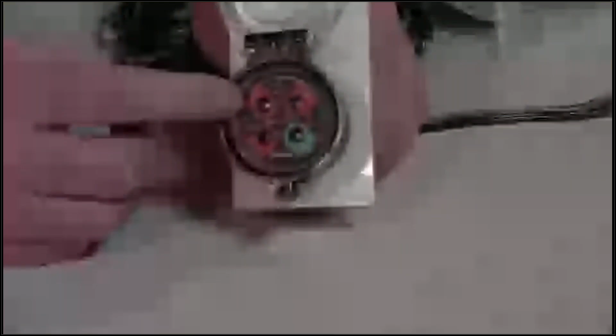Now, again, there's a little bit more involved with the live dead live test. We actually take it a step further, where we suggest testing your meter to a known voltage source, testing it live at the actual device itself, isolating the power, flipping the disconnect switch, testing it dead at the actual device itself, and then testing again your meter to a known voltage source. So that is what we call a live dead live test. Again, associating that back to NFPA 70E and enhancing that compliance.